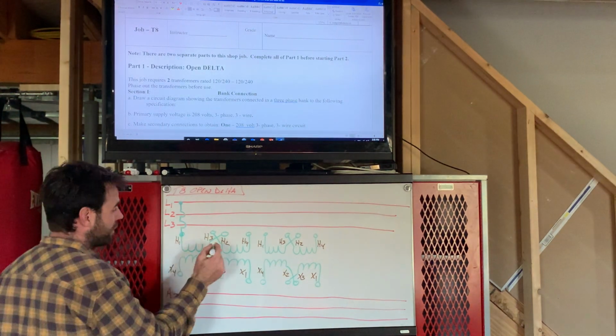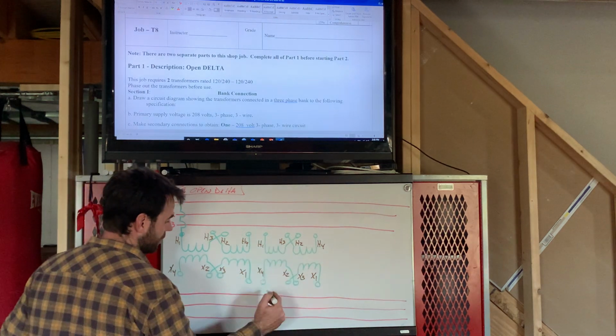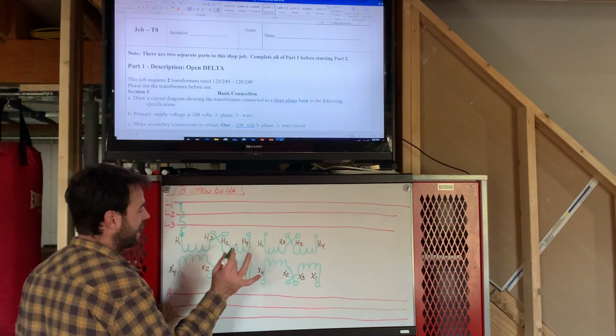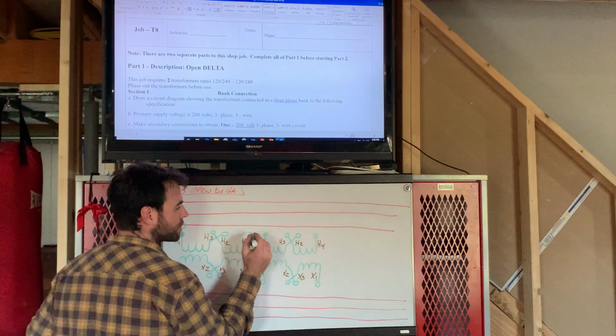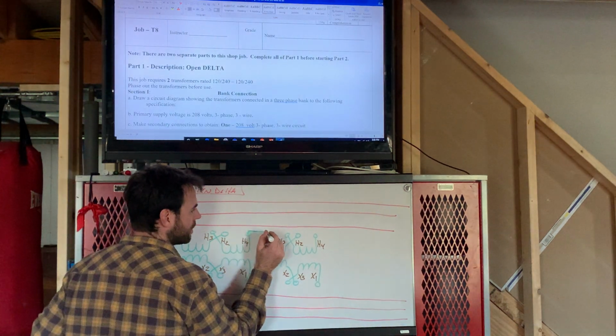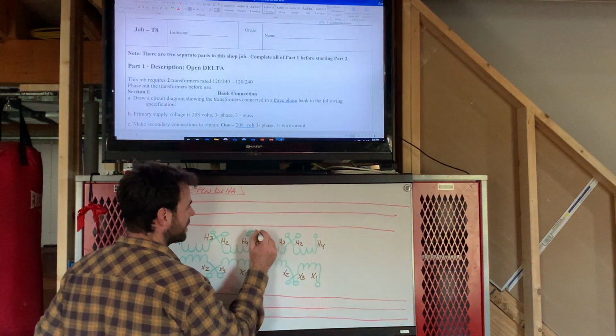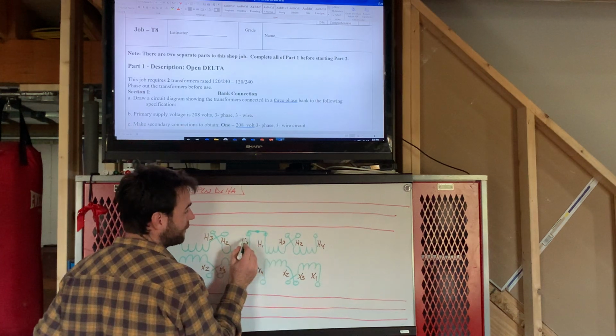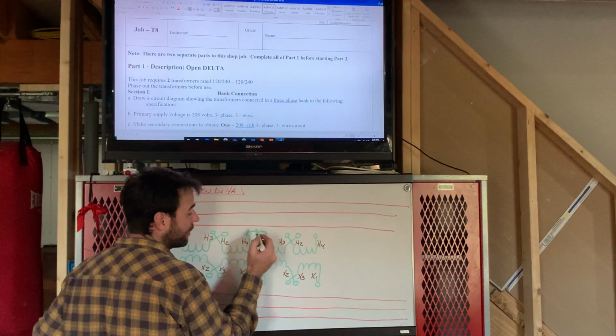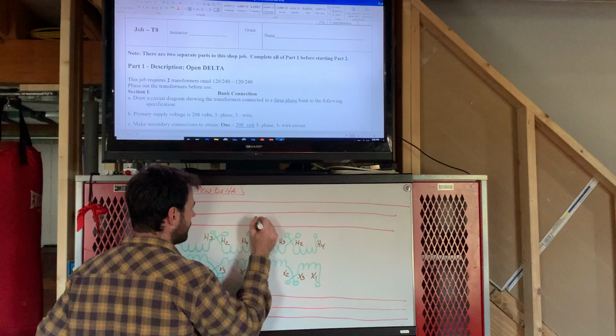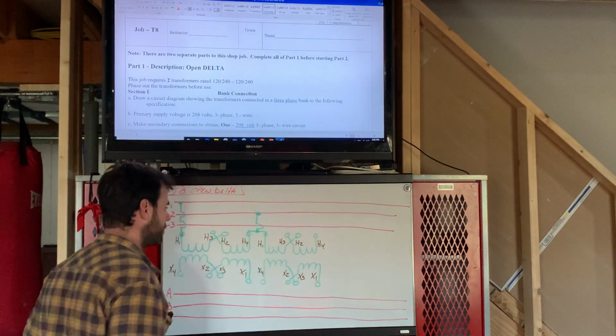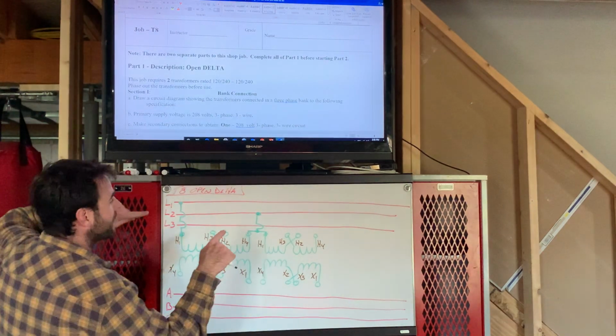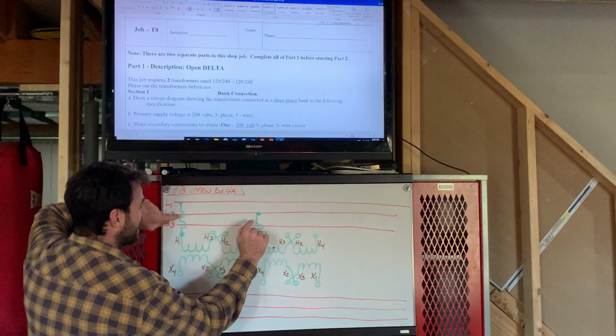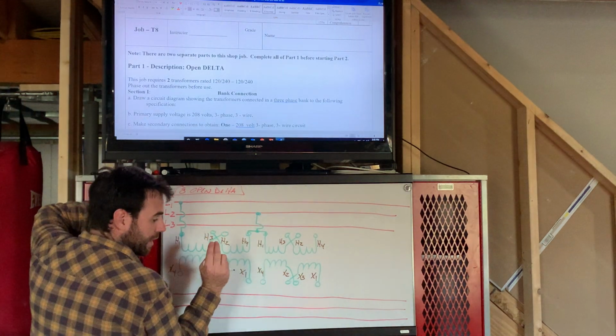Okay? H1 of transformer 1, this is transformer 2. Then what we're going to do is connect transformer 1 to transformer 2. So we're going to jump H4 to H1, and we're going to bring this jumper up, either off of H4 or off of H1, doesn't matter after the tied common, come up, go to line 2. So now essentially we're bringing line voltage between line 1 and line 2, 208, into this transformer.